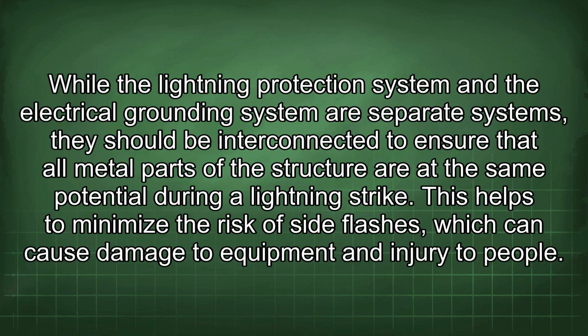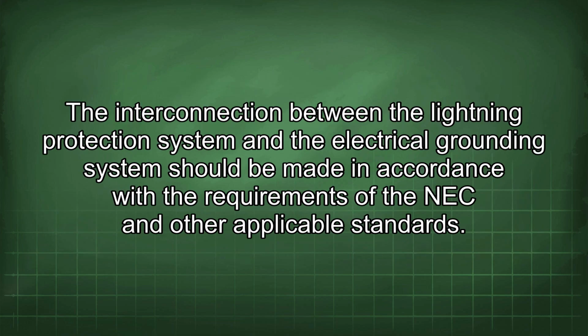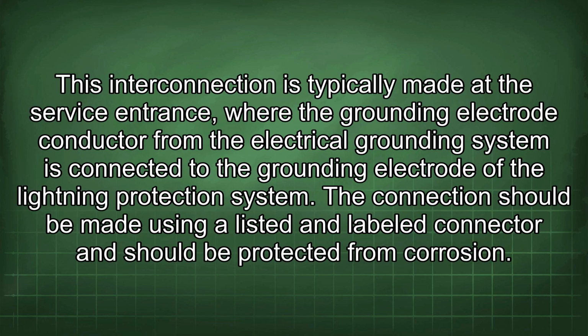While the lightning protection system and the electrical grounding system are separate systems, they should be interconnected to ensure that all metal parts of the structure are at the same potential during a lightning strike. This helps to minimize the risk of side flashes, which can cause damage to equipment and injury to people. The interconnection between the lightning protection system and the electrical grounding system should be made in accordance with the requirements of the NEC and other applicable standards. This interconnection is typically made at the service entrance, where the grounding electrode conductor from the electrical grounding system is connected to the grounding electrode of the lightning protection system. The connection should be made using a listed and labeled connector and should be protected from corrosion.